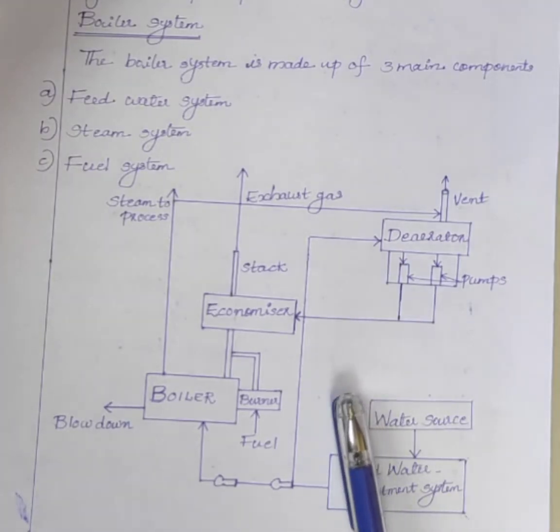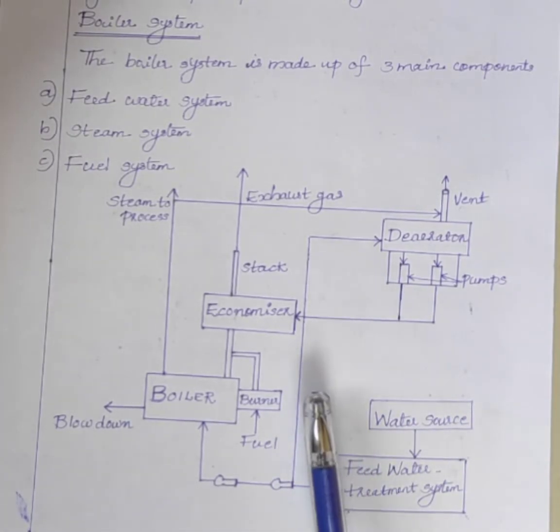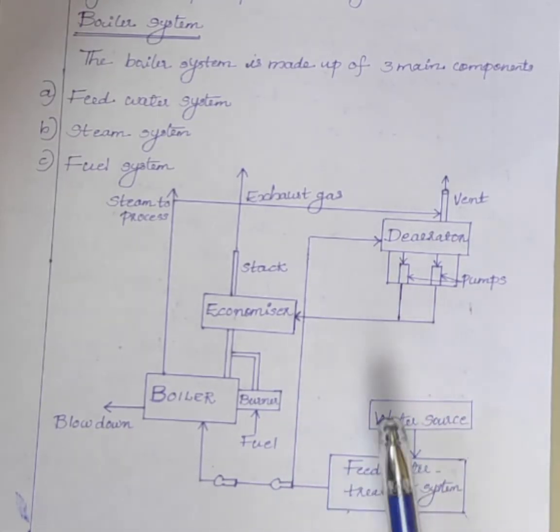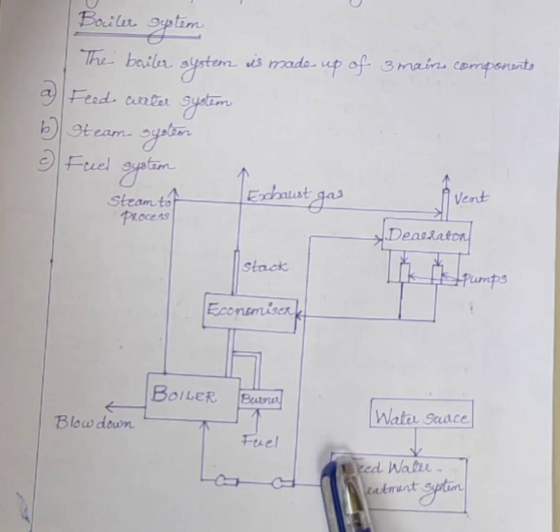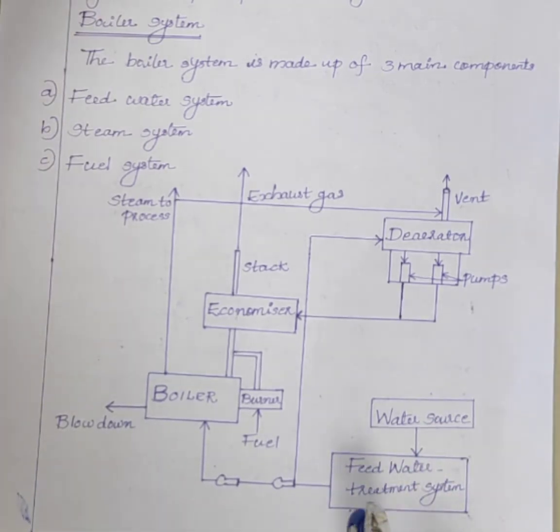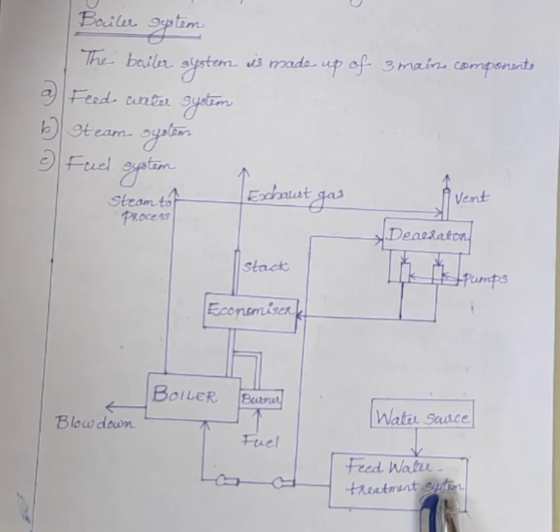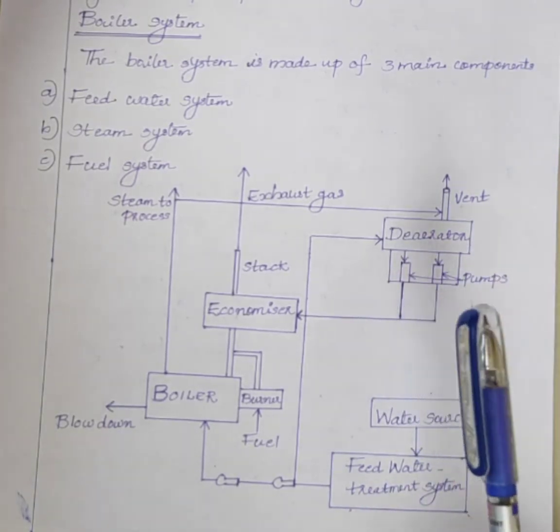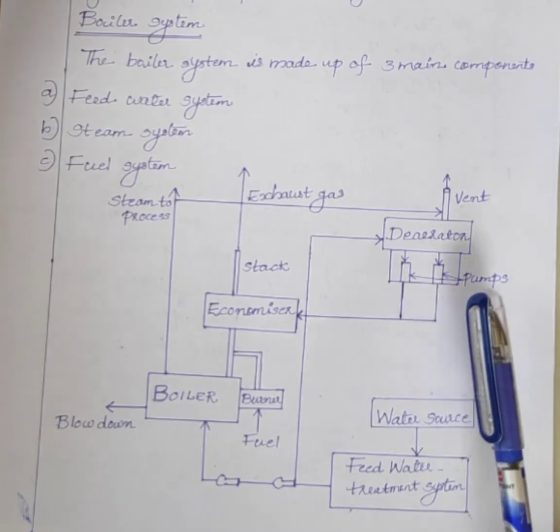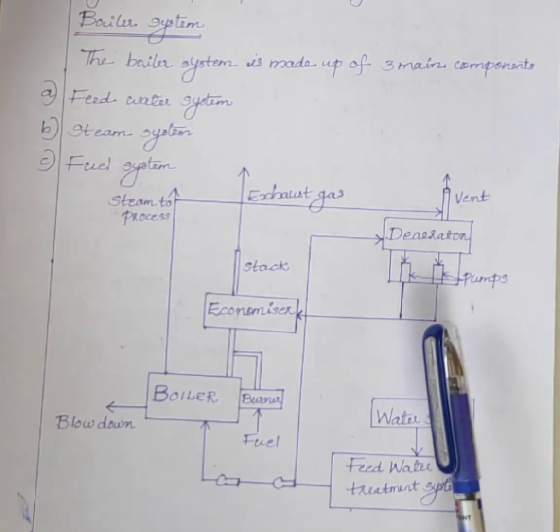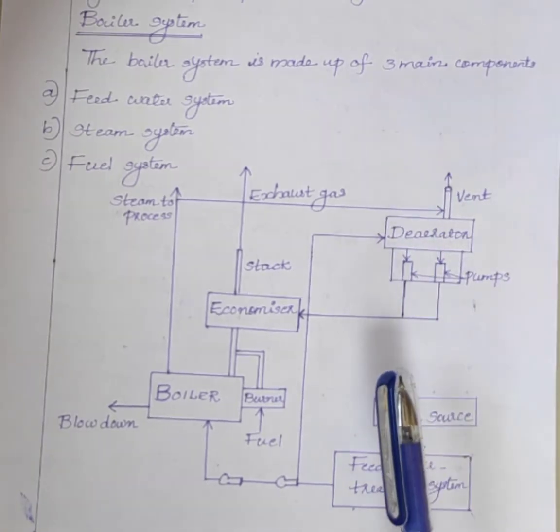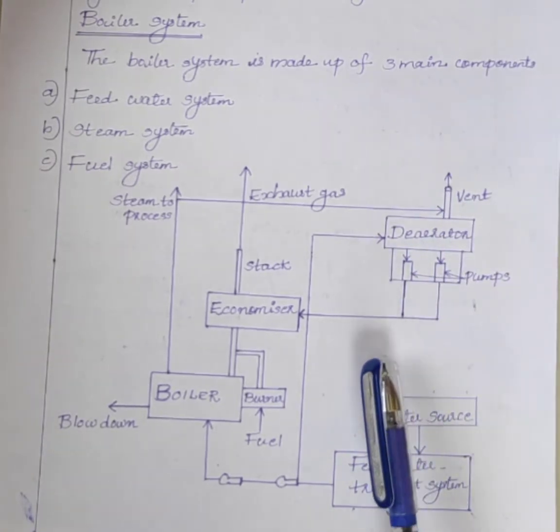There are two main sources of feed water: first one is condensate or condensed steam, and second one is make-up water or treated raw water. In boiler feed water system, a feed water treatment system is used to remove dissolved solids, suspended solids, and organic materials from the feed water. The deaerator removes dissolved gases from the boiler feed water and protects the steam from the effects of corrosive gases. The feed water treatment system ensures an efficient process and quality steam generation.